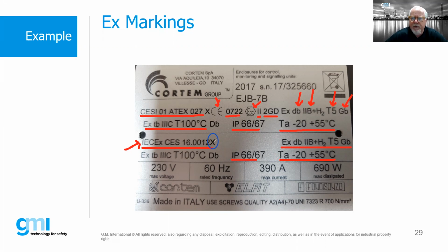Now, the condition for safe use for this particular product, since this is a flame-proof product, could state something to the effect of all glands must be installed in accordance with 60079-14, or it must be installed in a particular fashion, or what have you. So many times products will have X conditions, and as an inspector, when I go in and take a look, that's one of the first things I'm going to look for. I want to see the certificate, I want to see that X condition, and then I want to check the installation.